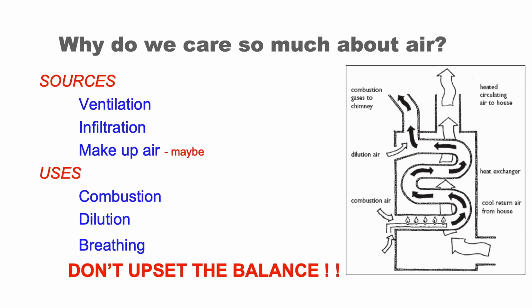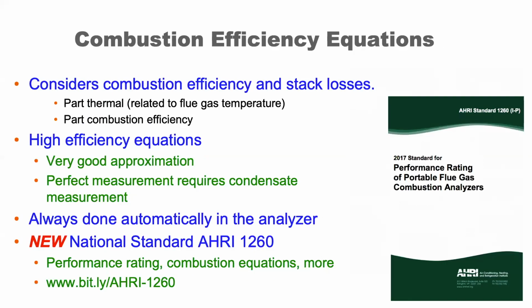And I've actually worked on some expert witness cases where that's been done, where they really sealed up. This was a manufactured house. They really sealed it up tight, and they caused a furnace that wasn't operating poorly before to actually poison someone because it was using infiltration air in its combustion process. So you have to be very much aware of the air.